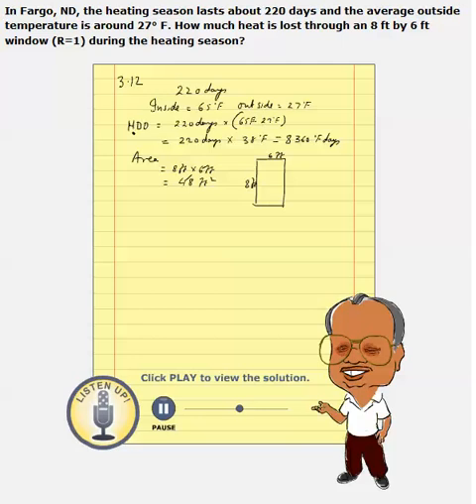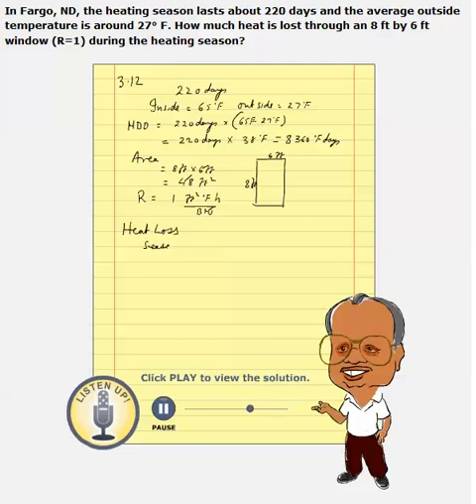We know the temperature difference. We know the heating degree days. We can calculate the heat loss provided we have the R-value. The R-value is also given: 1 foot squared degree Fahrenheit hour over BTU. Heat loss through a season is equal to area times HDD times 24 over R.